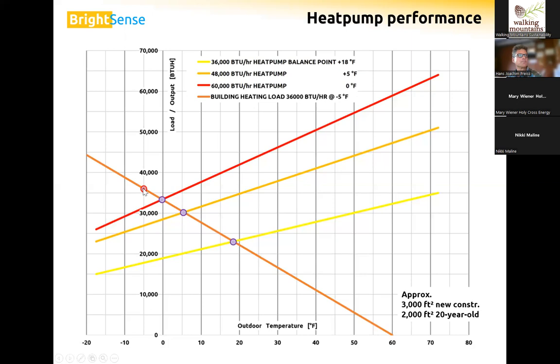So the warmer it is, the lower our heating load, and the colder, the greater. And then these three other lines here, those are the outputs of three heat pump sizes: nominal 36, nominal 48, and nominal 60,000 BTU heat pump. I say nominal because those are measured at 47 degrees. That is an industry standard. 47 degrees is a measurement for air source heat pumps, also mini splits.